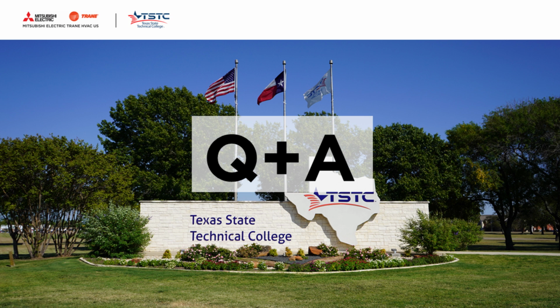Sure, I can speak to that. Is it possible? Sure. I don't know that it would necessarily be needed. There are some hard limits. For example, if you had one condensing unit, there is a maximum of 50 indoor zones that could be connected to that one condensing unit. Now, we don't recommend that. Typically, there's a real efficiency sweet spot for VRF systems in the 8 to 10 ton zone. And again, that's my sales guy speak, so forgive me if I'm a little off on my tonnage.